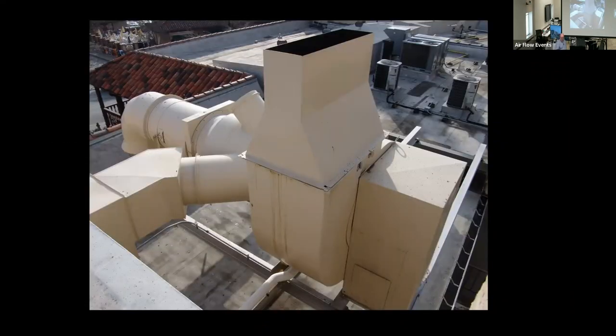But yeah, so this got added, and it's a manual damper to try to add more air to balance the turbulence when it goes in there. That's a clean out port. Tom hit it right on the head as far as grease.